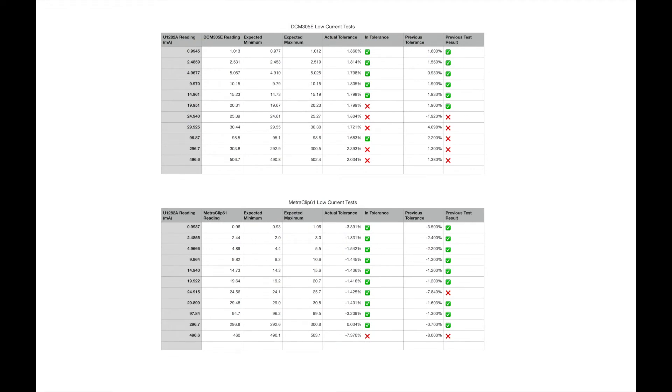Okay, so here are the two tables of test results. The tests that I've done this time around are all in the left-hand columns with the actual reading I took from the U1282A as the cross reference, and then the reading from the instrument. In the in-tolerance column, you can see where the reading is actually in tolerance or out of tolerance.